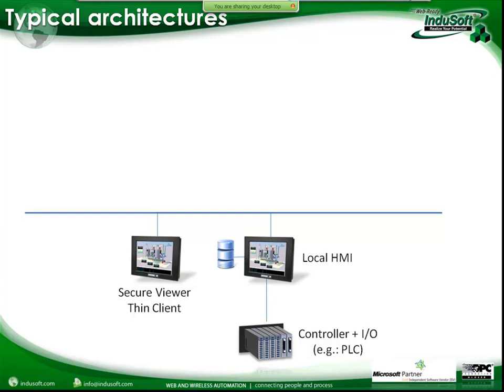Operators can operate each of the two HMIs individually and open different screens on each at the same time. You do not have to install the license on the Secure Viewer Thin Client — the license is installed only on the local HMI, and any runtime license for InduSoft supports one Secure Viewer Thin Client connected to the local HMI. If you need more than one Secure Viewer Thin Client connected simultaneously, you simply upgrade the license. The Secure Viewer Thin Client is a very affordable and flexible way to have more than one HMI for the same machine with no extra development effort and very little additional cost.